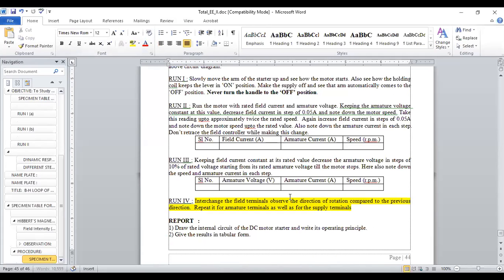So interchange the field terminals, observe the direction of rotation compared to the previous directions, and repeat for the armature terminals as well as for the supply terminals. So three combinations you have to check. First, we have to check by interchanging the supply terminals. Then you have to check the direction of rotation interchanging the armature terminals, and then by interchanging the field terminals. You have to observe in which change the direction of rotation changes.